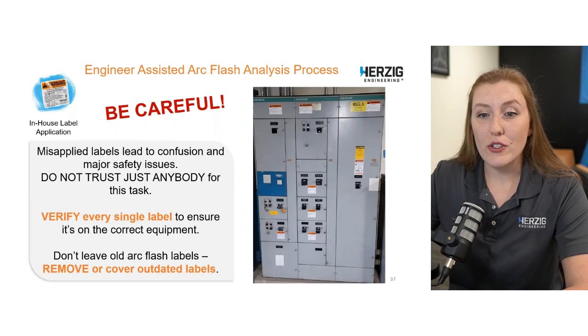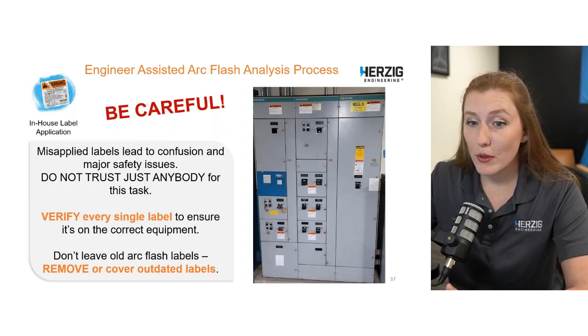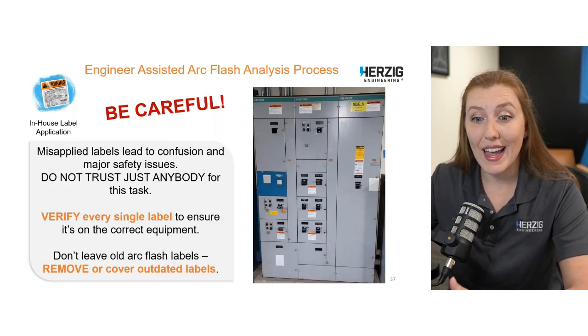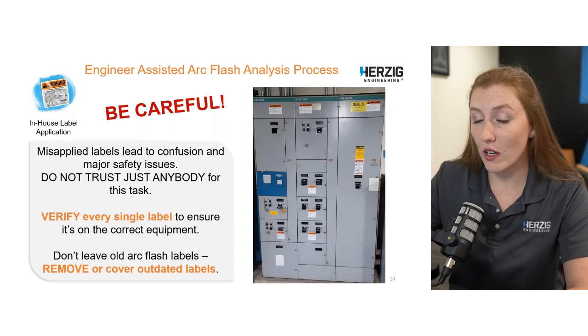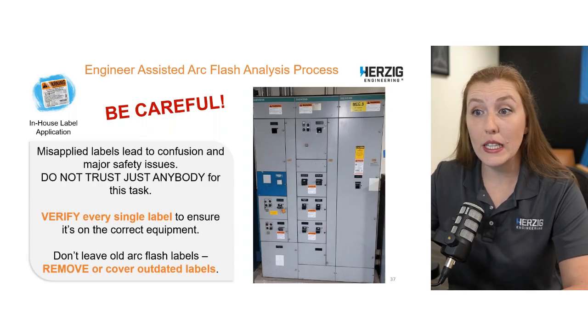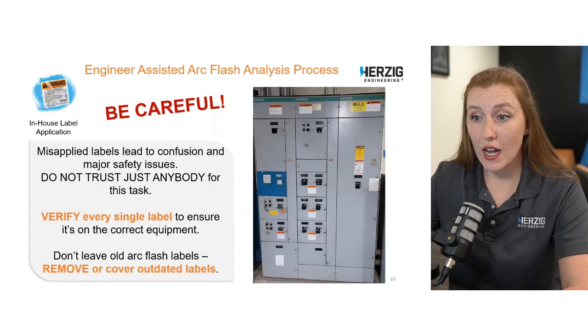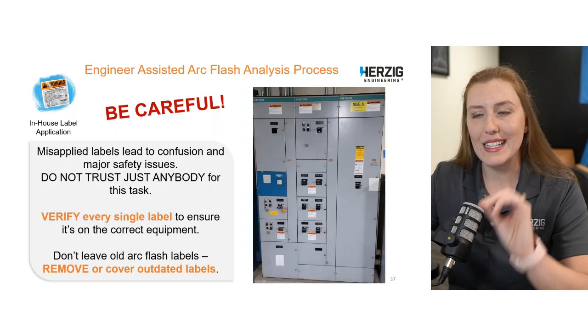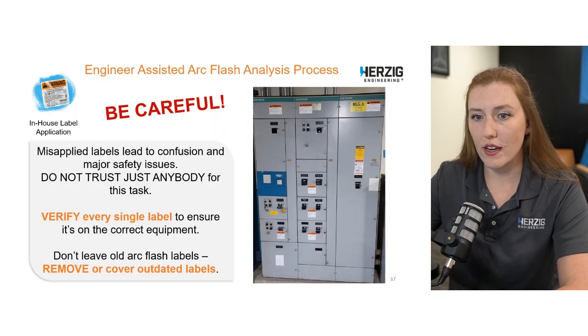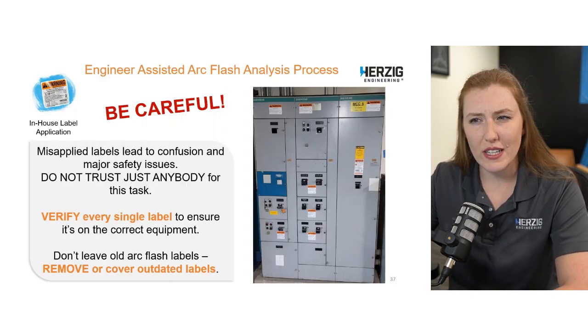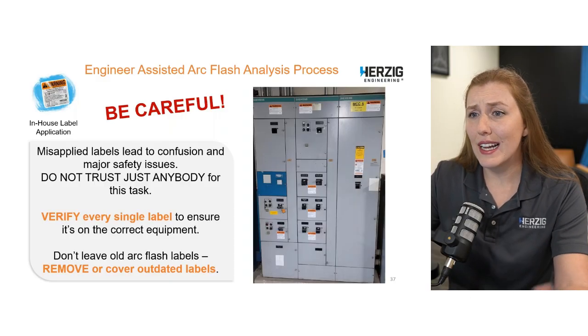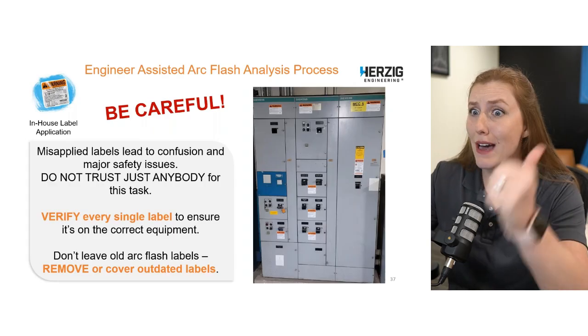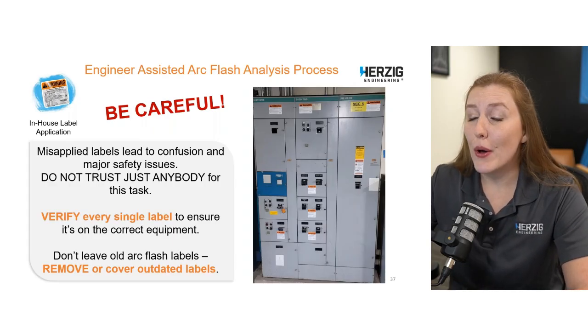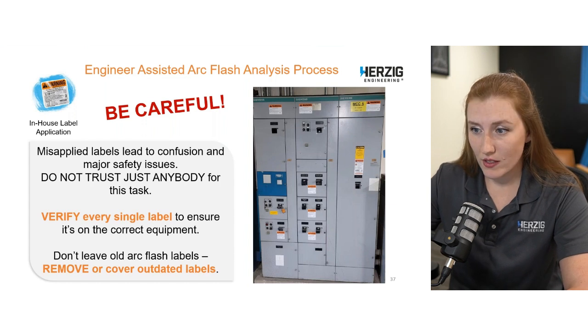So, you have to make sure that you verify every single label gets on the correct piece of equipment and you're not leaving old arc flash label information. So either completely remove it or cover it up or X it out or do something to make it clear that that label is not to be used, not to be relied on. Okay, so do not trust just anybody to do this. Don't hand the stack of labels to the new guy and say, have at it, give him a job. No, it needs to be someone that you trust.